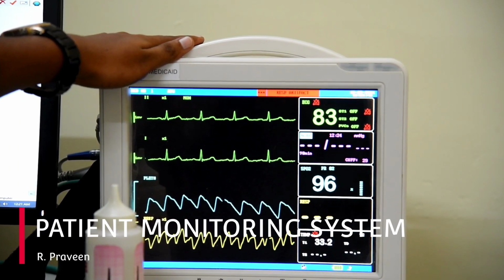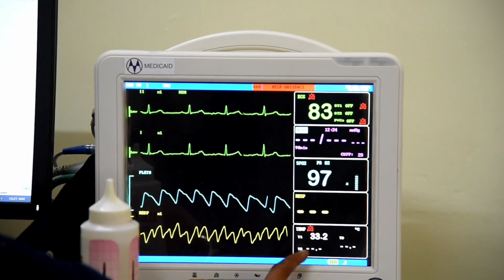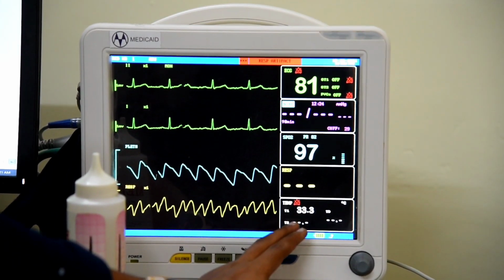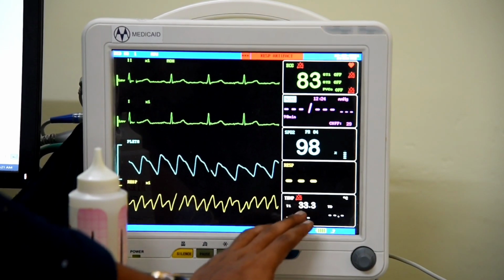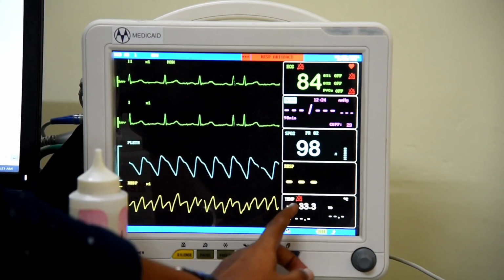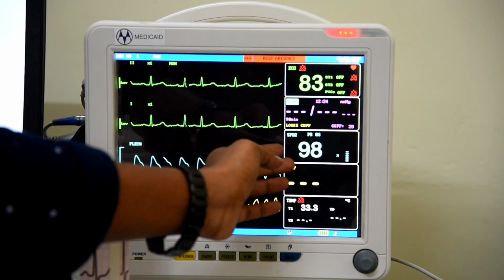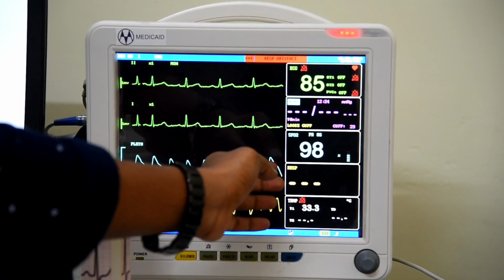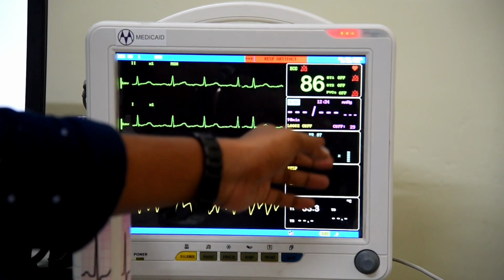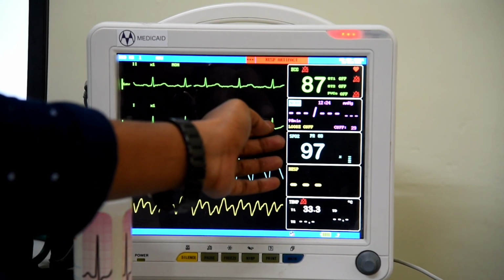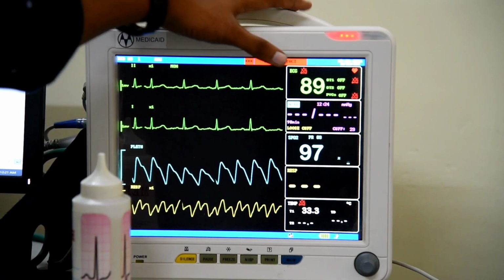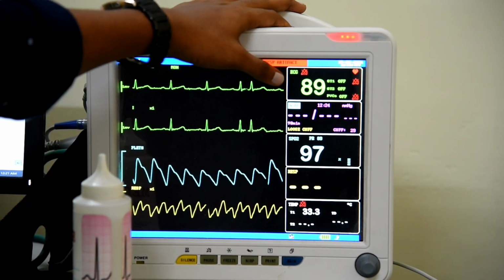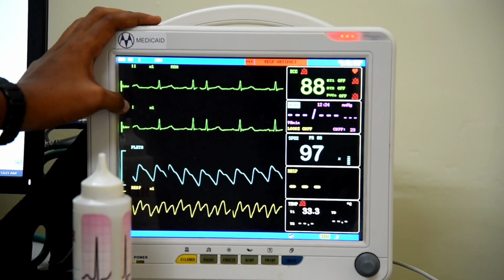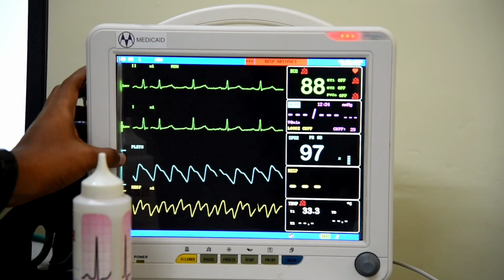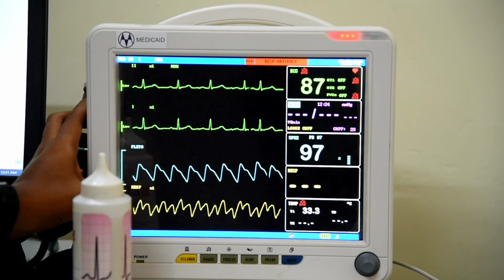Basically it is a 5-para monitor. Now we can see the temperature. The basic temperature is 33.3 and it is connected to the patient. Next we can see the respiration, and next we are seeing the saturation of pulse oxygen. It is a fingertip pulse oximeter, and a non-invasive blood pressure, NIBP. And next we have connected a 5-lead ECG, and we can see the 2 leads, lead 1 and lead 2, and now we can see plethysmography and the respiration.